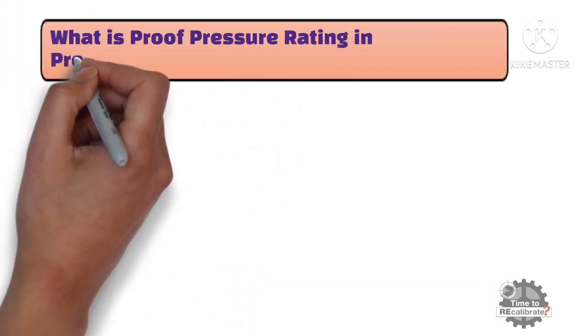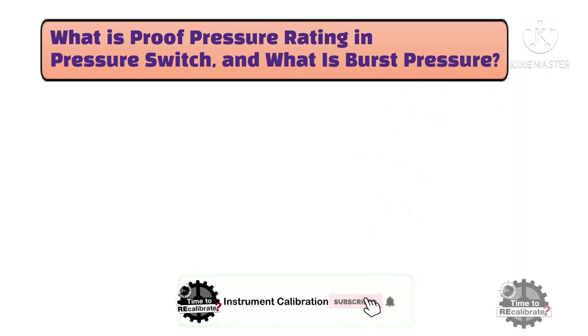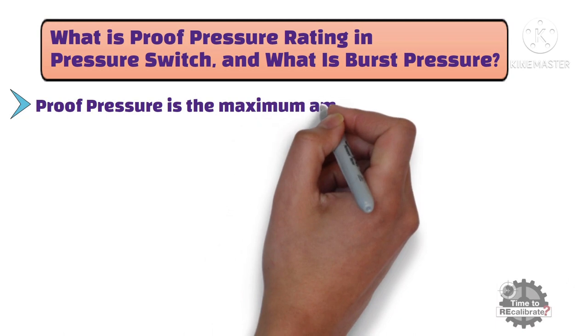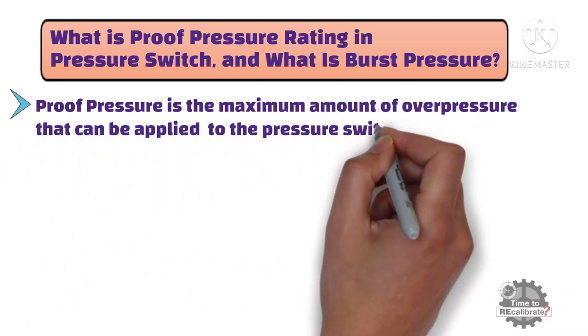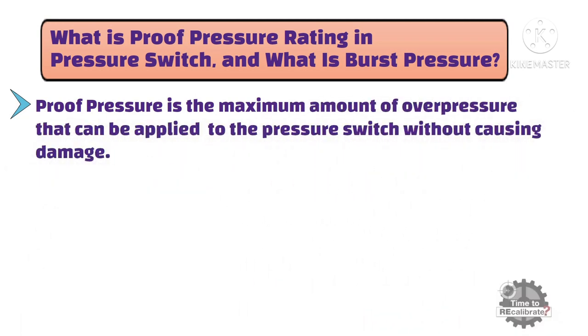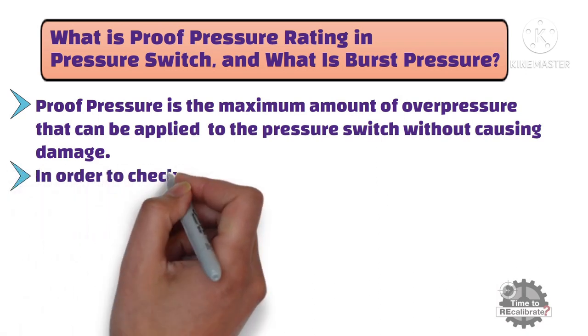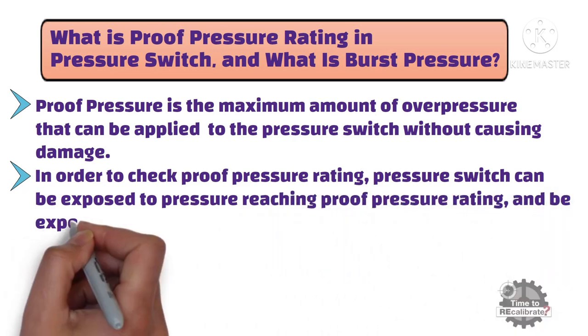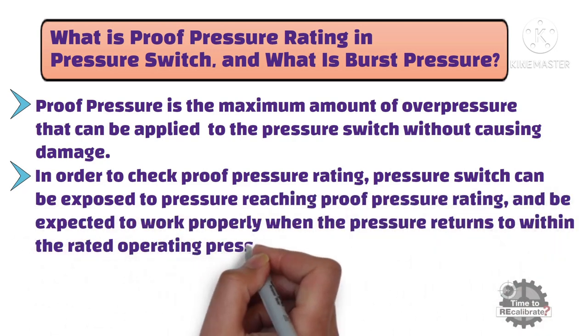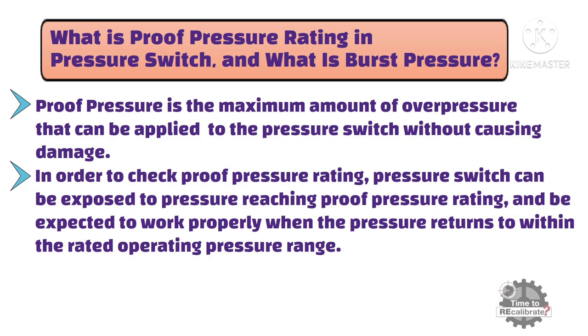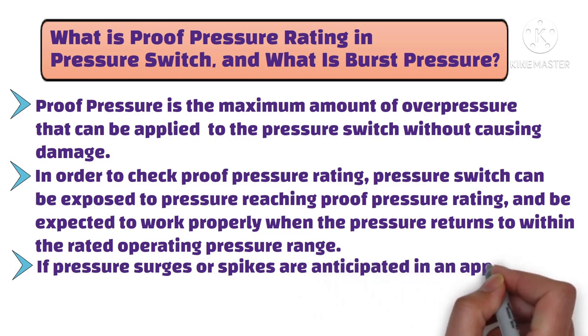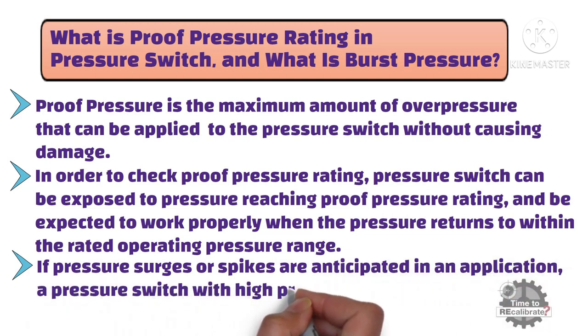Now, what is proof pressure rating in a pressure switch? Proof pressure is the maximum amount of overpressure that can be applied to the pressure switch without causing damage. The pressure switch can be exposed to pressure reaching the proof pressure rating and be expected to work properly when the pressure returns to within the rated operating pressure range. If pressure surges or spikes are anticipated in an application, a pressure switch with a high proof pressure rating should be selected to avoid damage.